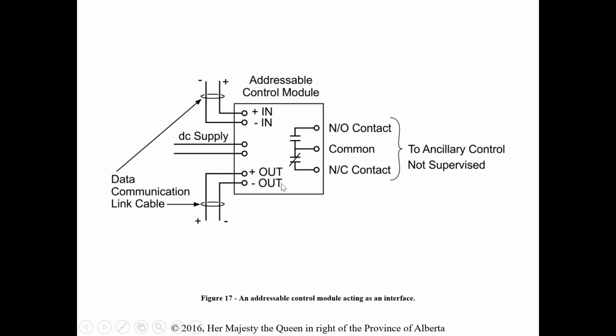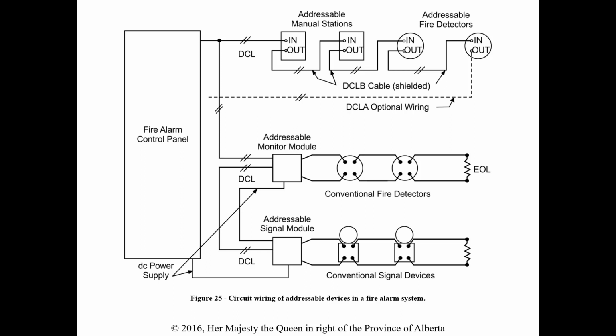The control module, also think of it as an addressable relay. Again, we have our DCL cables coming in, and now we could have ancillary control of non-supervised equipment. So a fan in a duct, a door magnet, that kind of stuff. So when something happens, this addressable control module can change the state of these contacts, either open or close, whatever the original state was, so that it either de-energizes or energizes things in the event of an alarm. Okay, so that's the three additional modules we're going to add potentially. And again, we do have these in our lab as well.